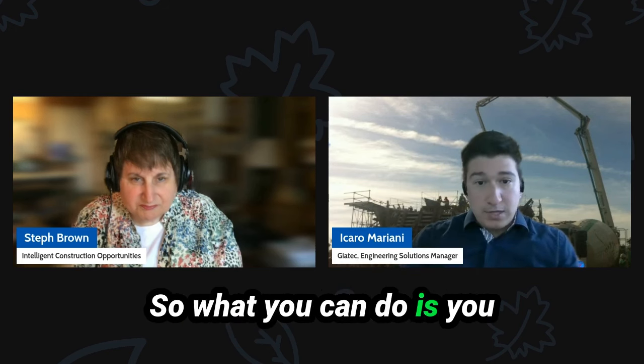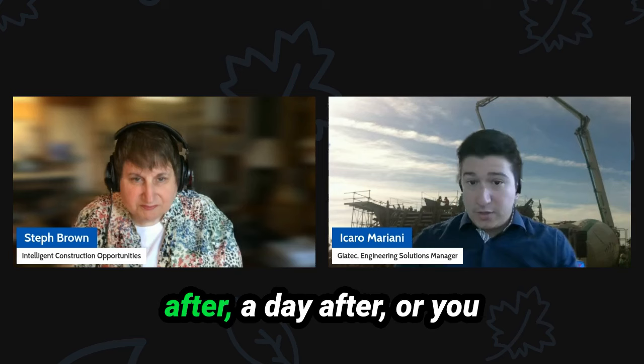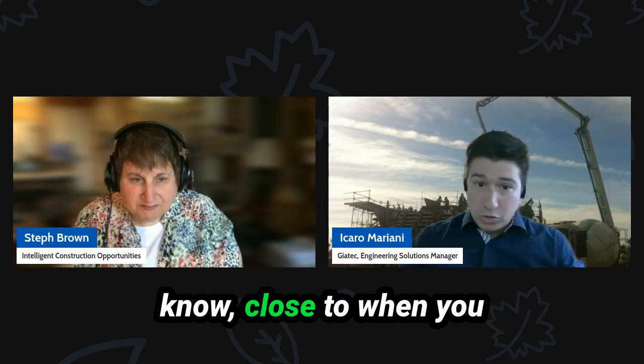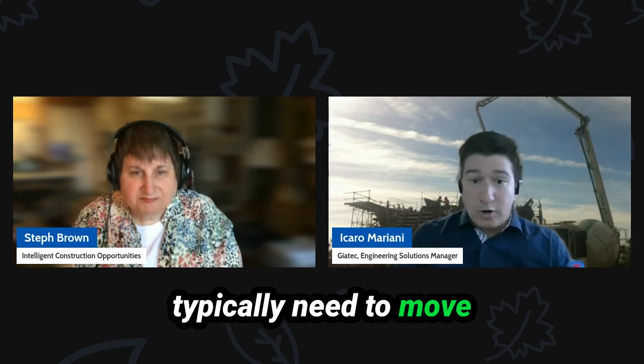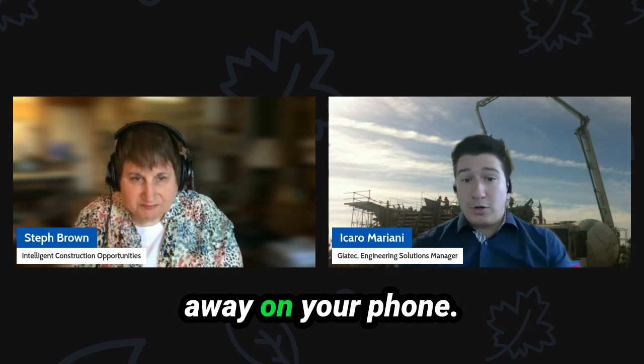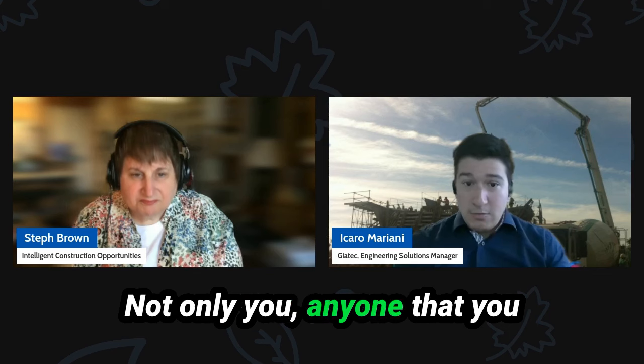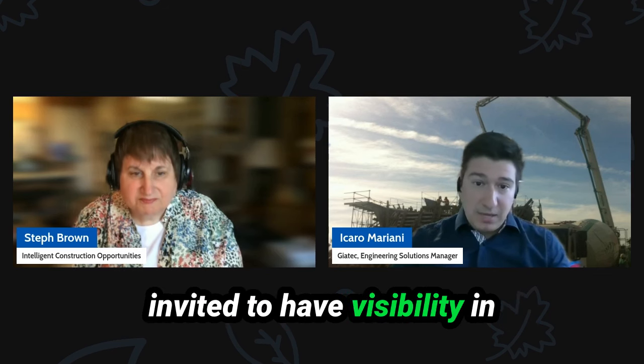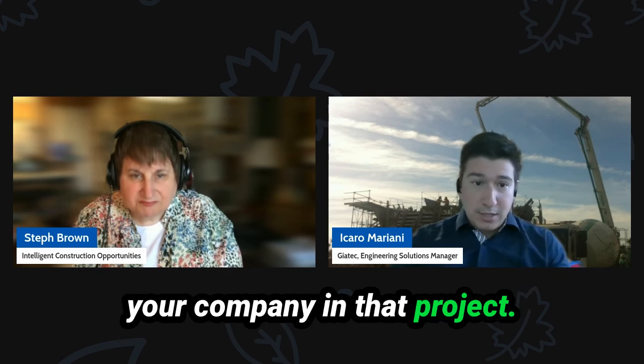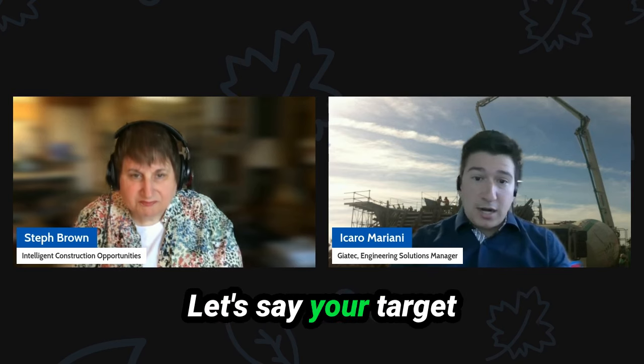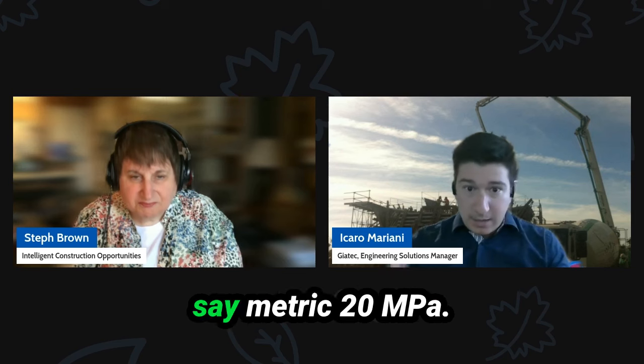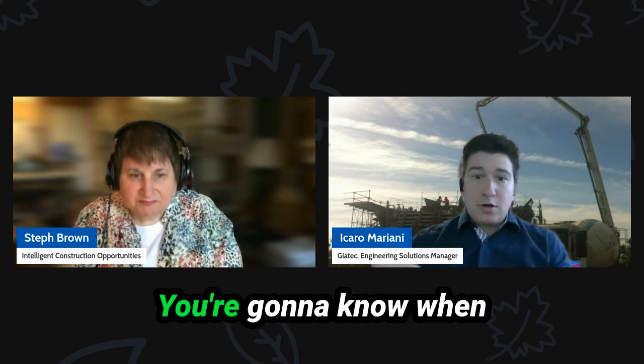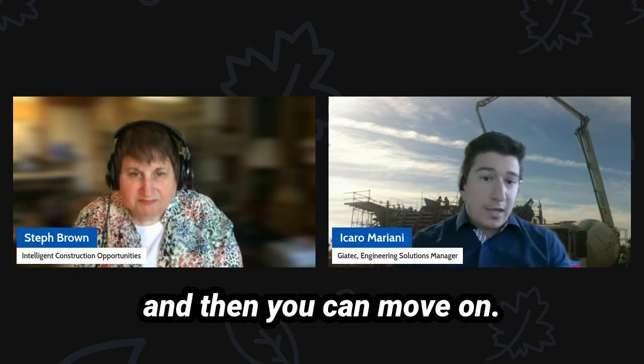So what you can do is you download the data an hour after, a day after, or close to when you typically need to move on, and see the data right away on your phone. Not only you, anyone that you invited to have visibility in your company in that project. You can set alerts. Let's say your target is a certain psi, or let's say in metric 20 MPa. You're gonna know when you reach that strength, and then you can move on.